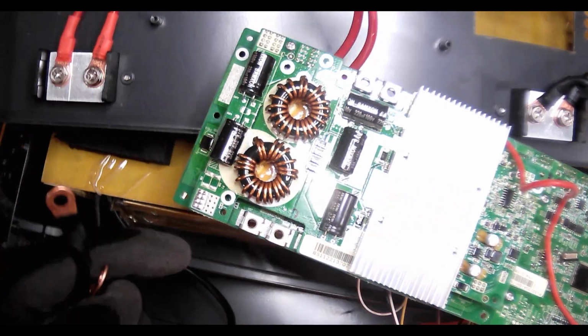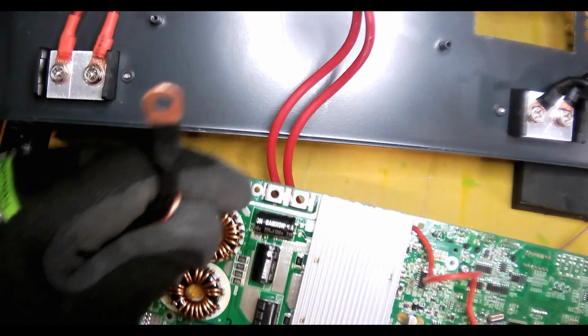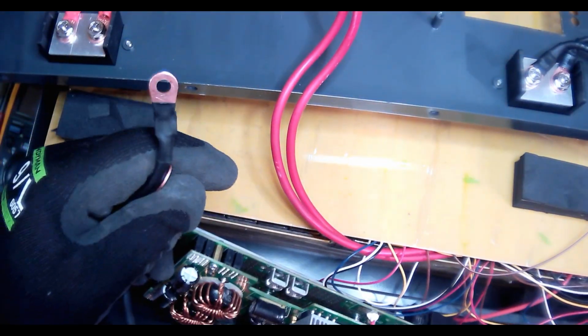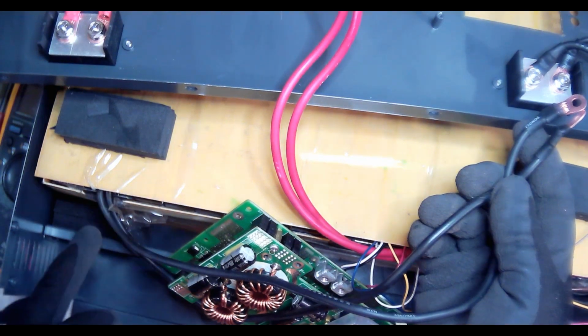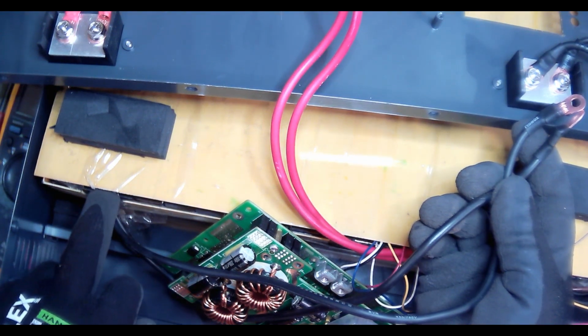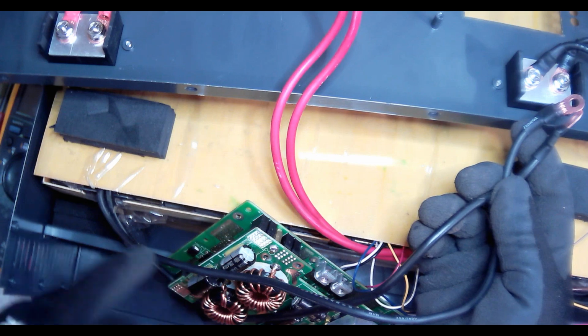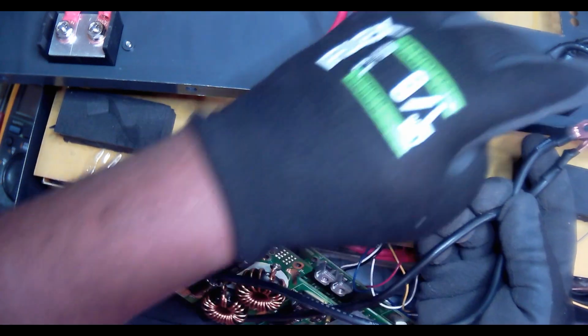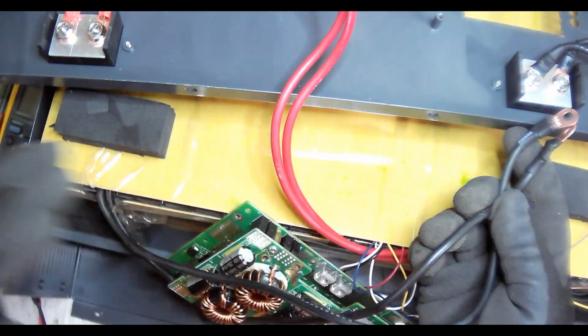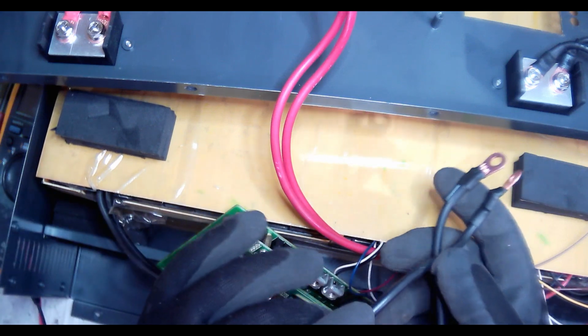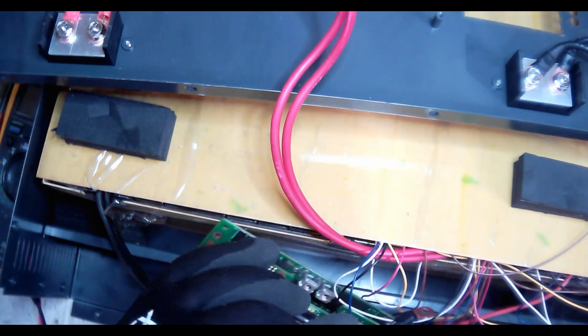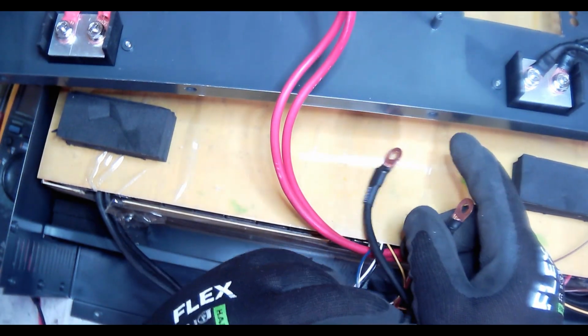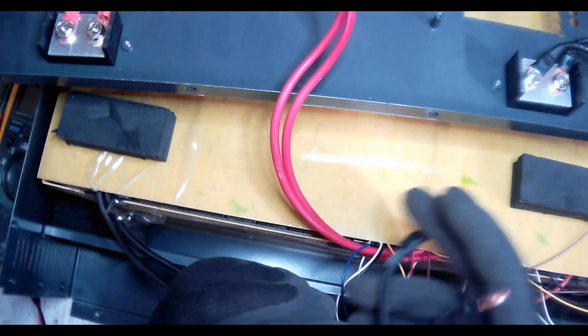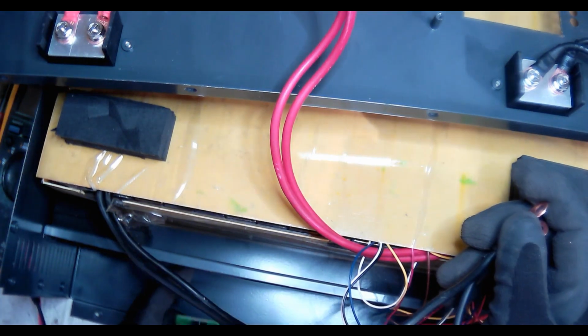So some other guys, what they do, they just short the output direct to there. So you see now the output is connected, bypassing the BMS, direct to the output. This is dangerous. Although you've got 48 volts and the system will work, it's not protected at all. That's very, very dangerous, because you bypass the card.